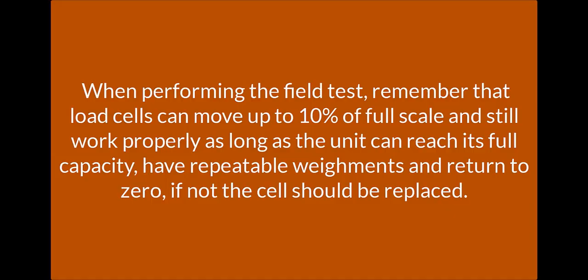When performing the field test, remember that load cells can move up to 10% of full scale and still work properly, as long as the unit can reach its full capacity, have repeatable weighments, and return to zero. If not, the cell should be replaced.